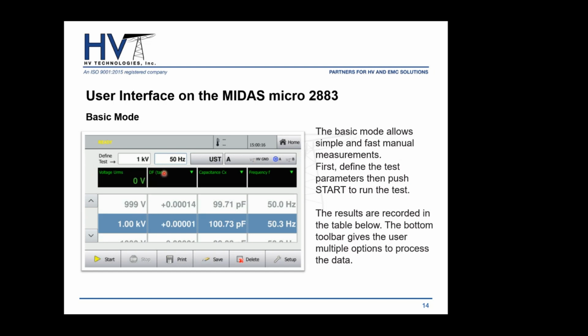These values here with the arrows pointing down are drop down menus that you can press, and you can choose which values you want to see and record at that moment. Usually you'll have one for tan delta, one for capacitance, and here you can do frequency or you can do inductance. There's a whole list of different measurement options that you can choose. So this is basically a one-shot test: easy, simple, fast, not too much science to it.